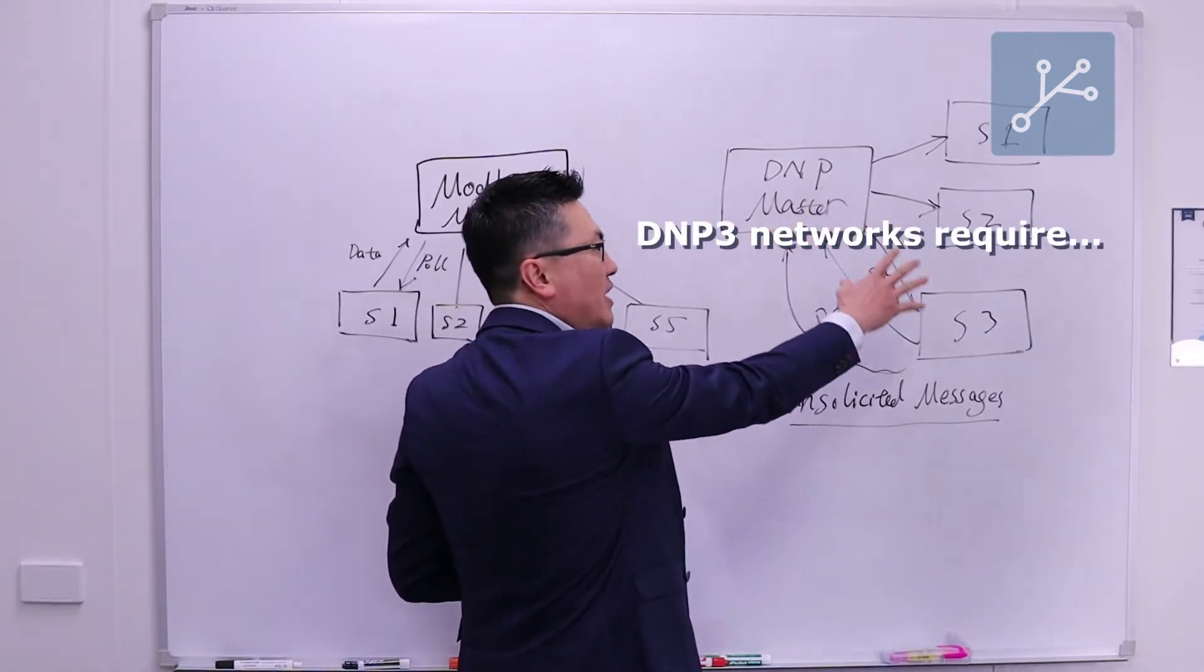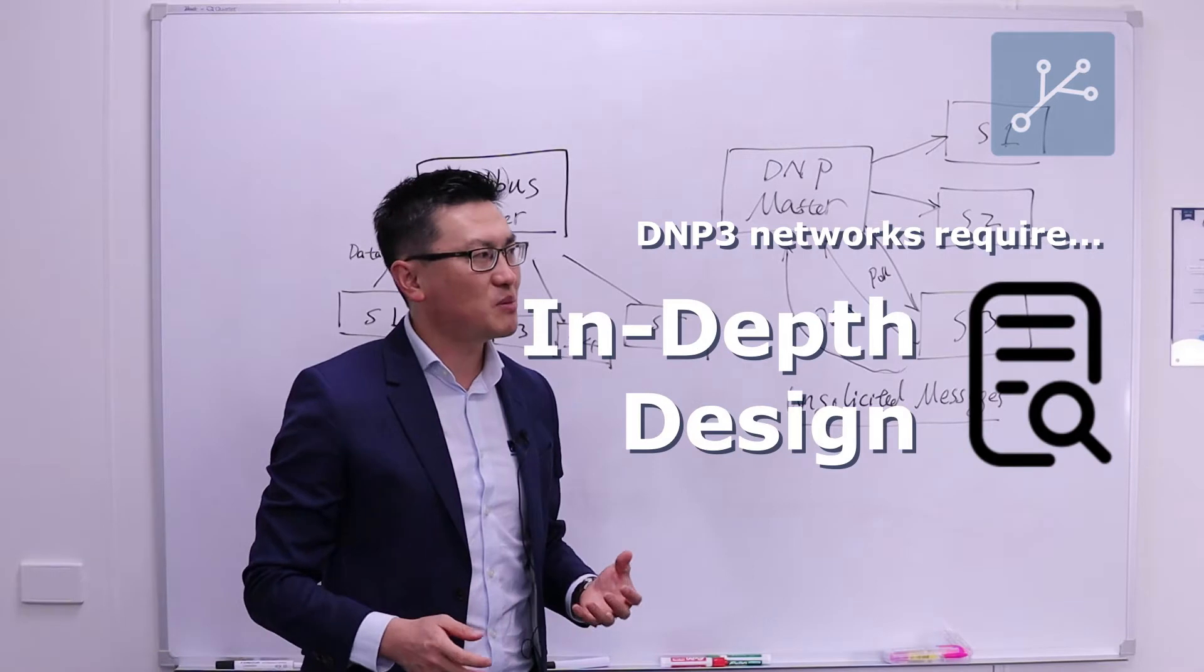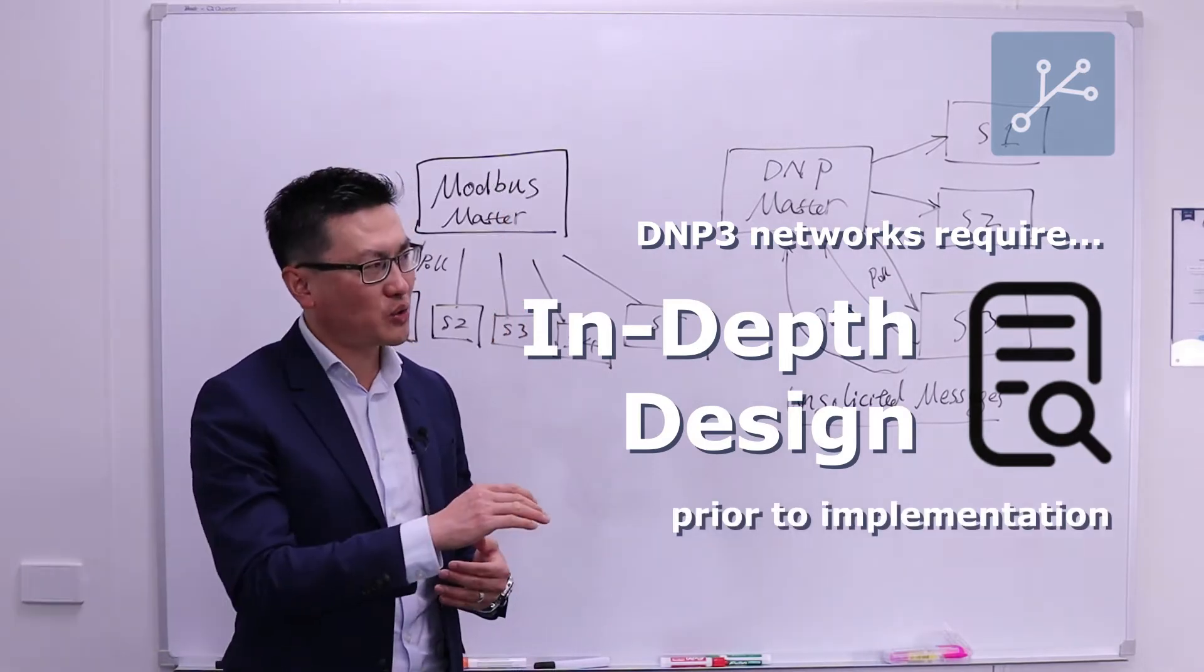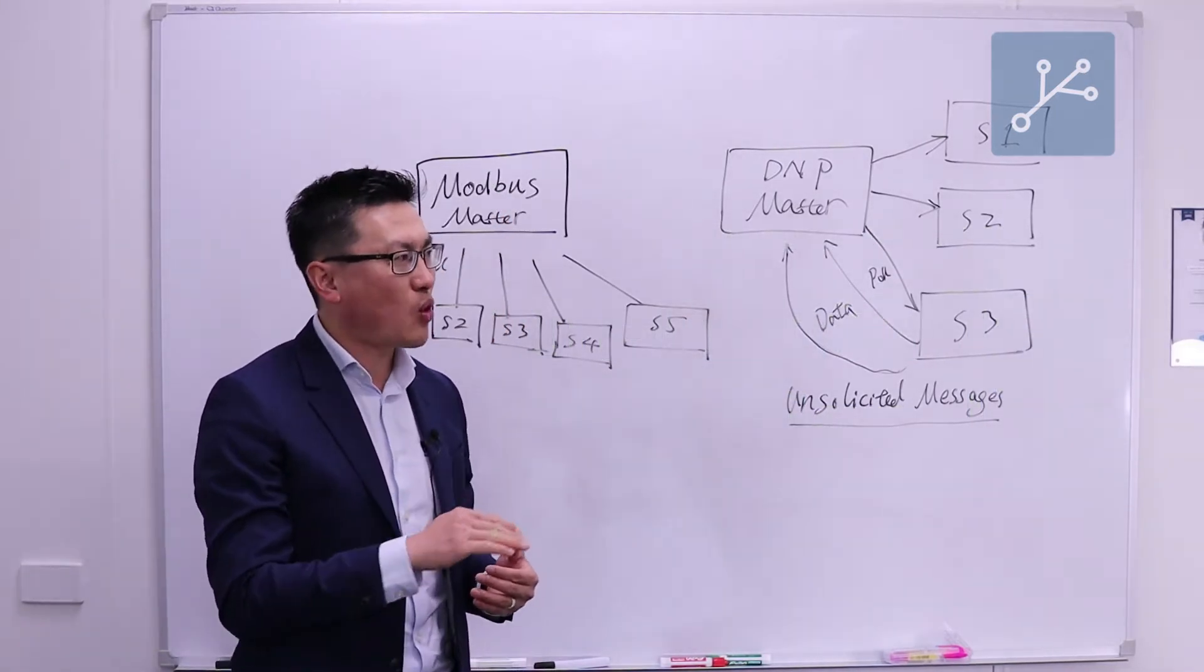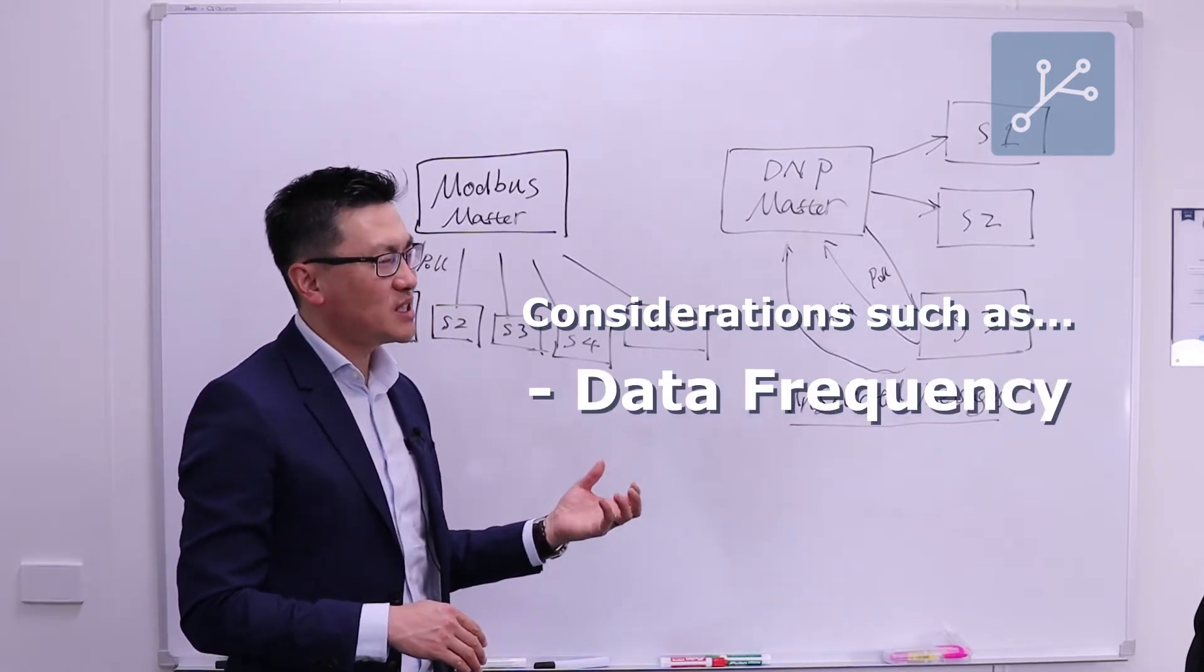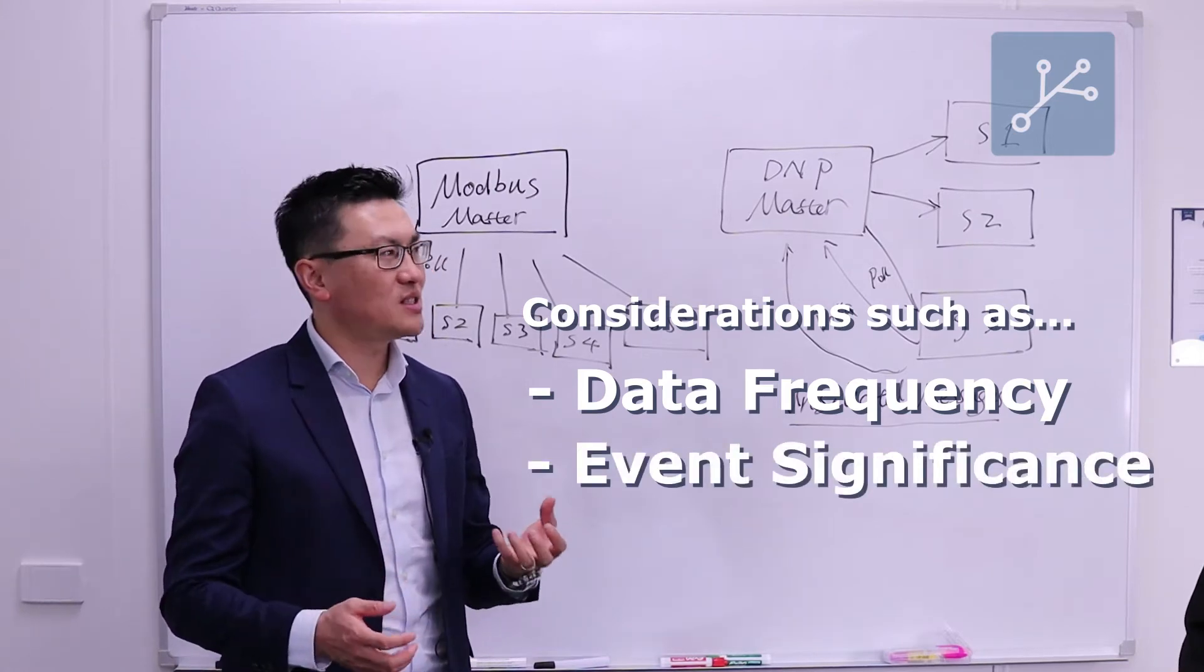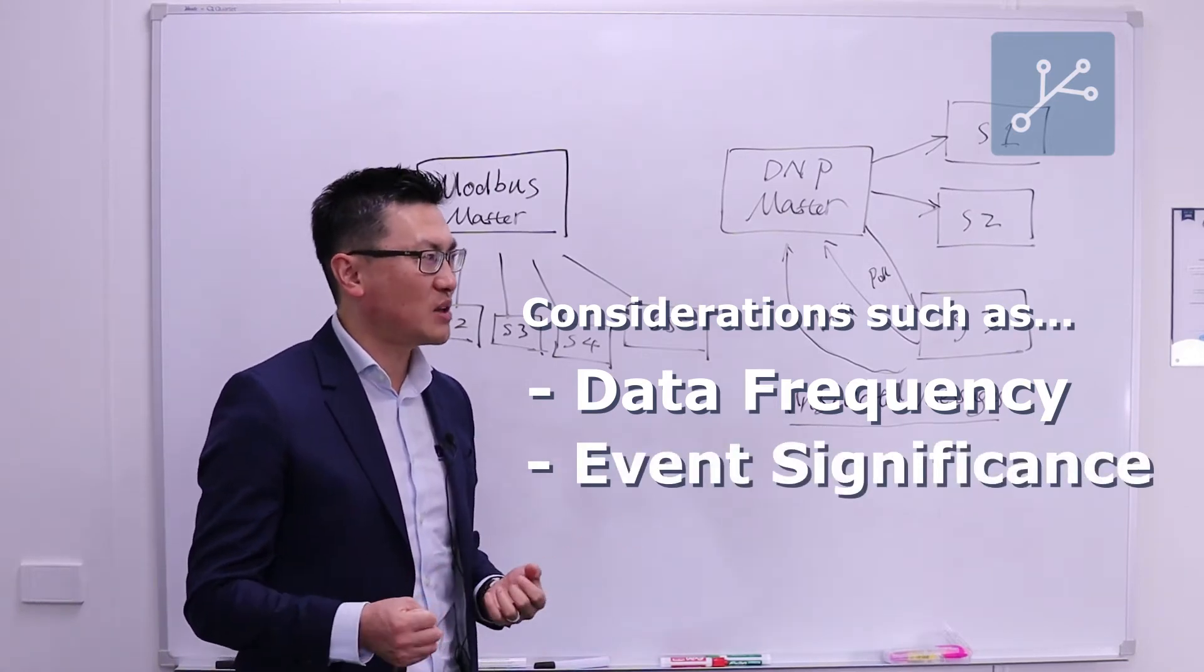That's why the DNP3 network usually requires a very in-depth design before implementation, going through the client's specification and requirements to find out exactly how often the clients want to see the data and alarms from each site, and how important those data are to the clients.